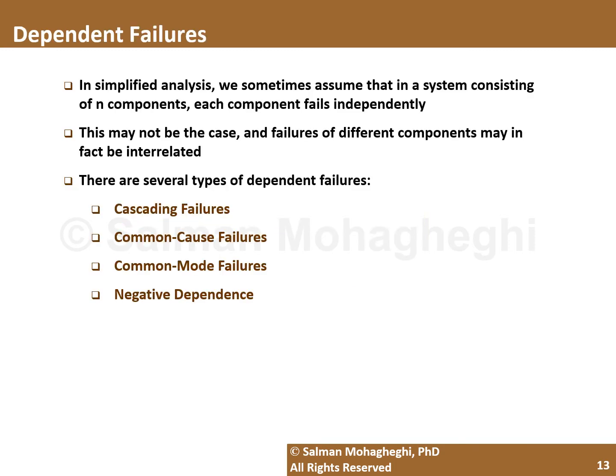Okay, now that we know the basic definitions of failures and faults, let's talk about a very important aspect of reliability theory, and that's dependent failures in interconnected systems. In most simplified analysis, when you have a system that consists of multiple components, you often assume that component failures are independent, meaning that if one component fails, it has no impact, positive or negative, on the chances or likelihood of failure of other components. While this is okay in simplified analysis, the assumption may not be true in real life.